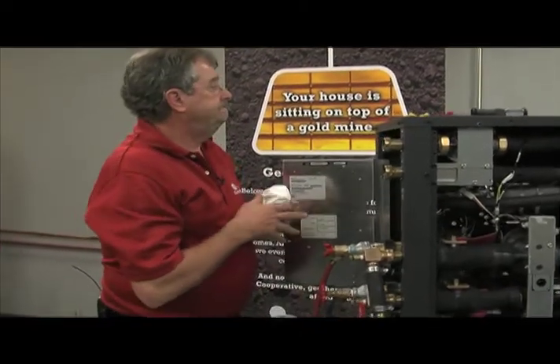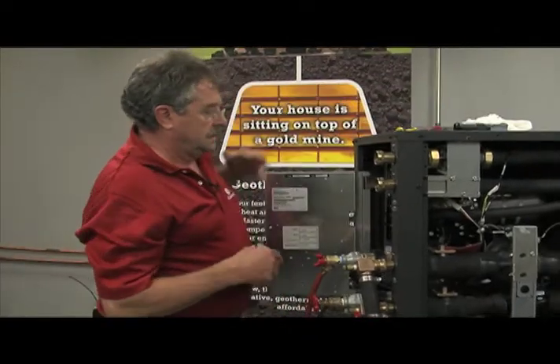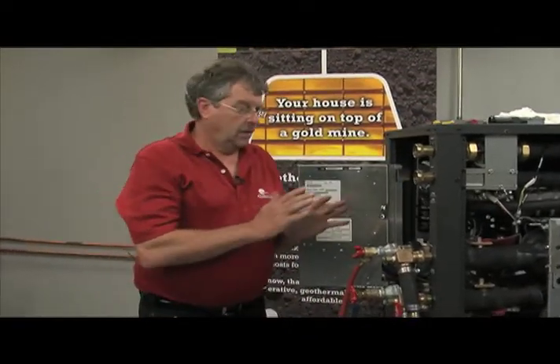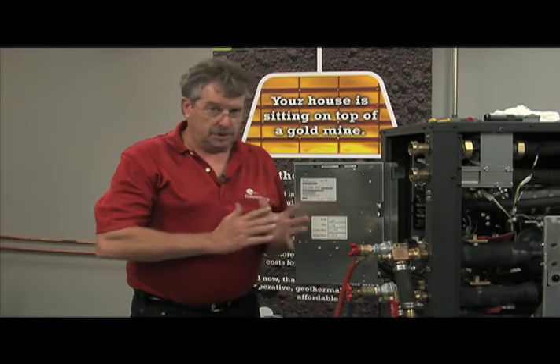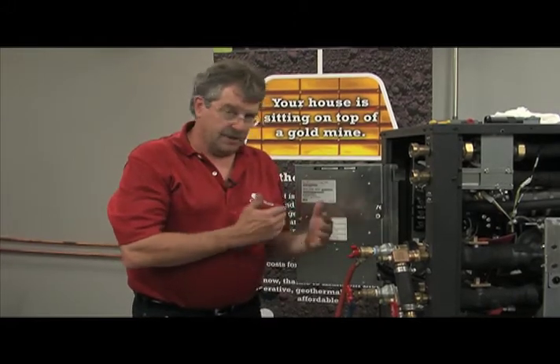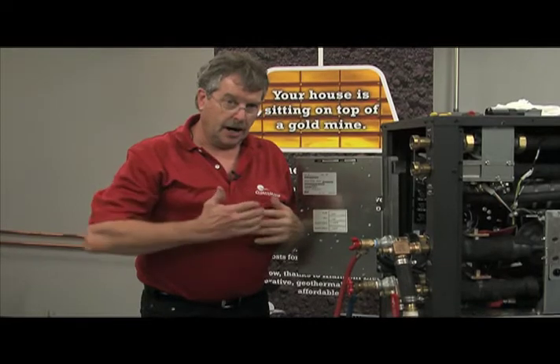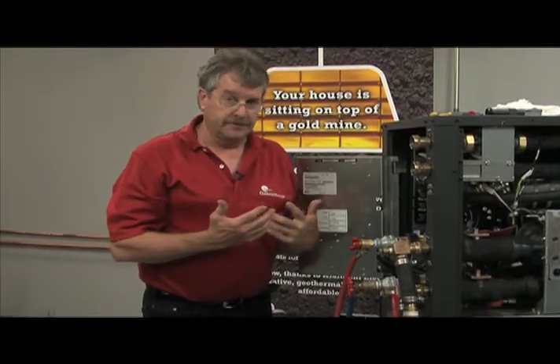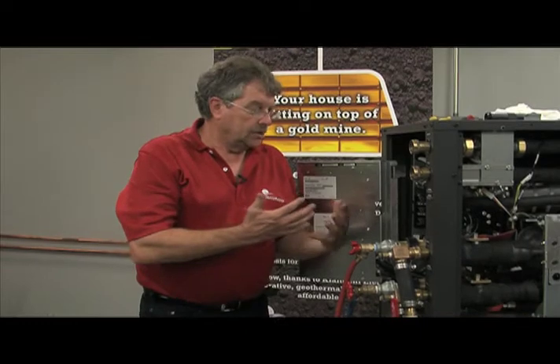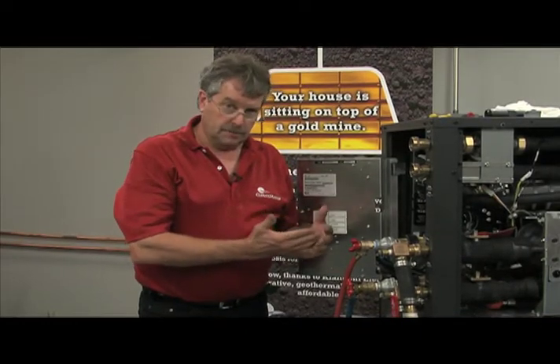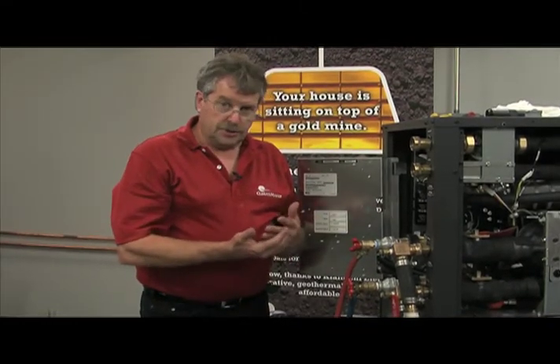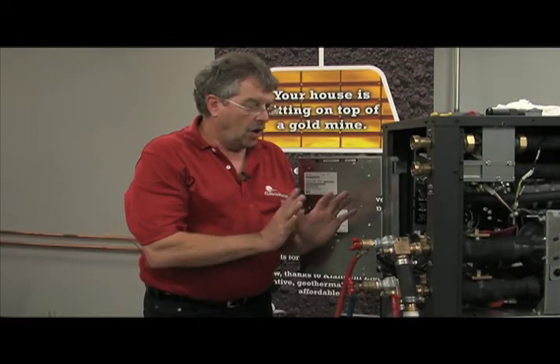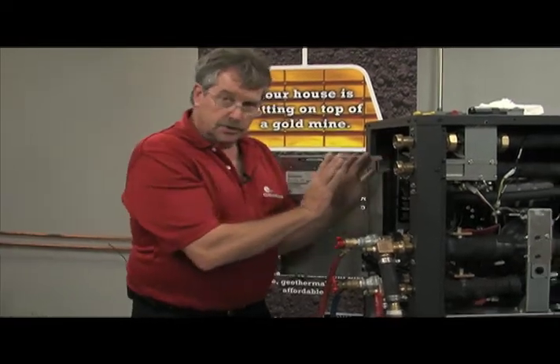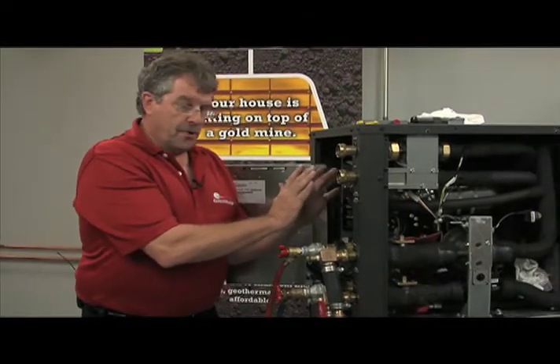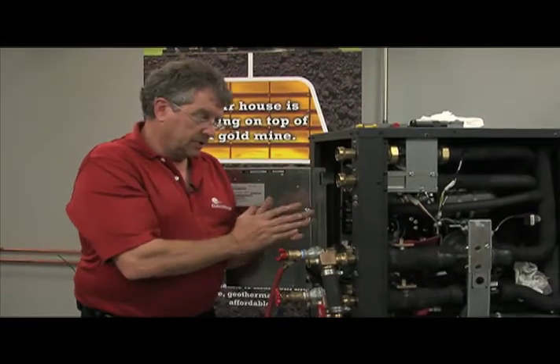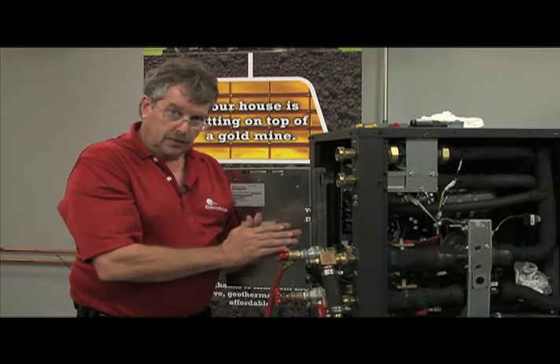So, last step. We've replaced our sensor, but we've introduced a little bit of air into the system. It's not likely there's a big pocket of air behind that flow sensor, but I'm always going to err on the side of being very conservative and safe because I don't want to keep doing this. So I'm going to go ahead and burp the system, but because I've retained the loop pressure and didn't compromise that, I isolated it. All I need to do is just gently and slowly flood and then burp just the unit side, pressurize it, pressurize the expansion tank, and then I can go live with the system.